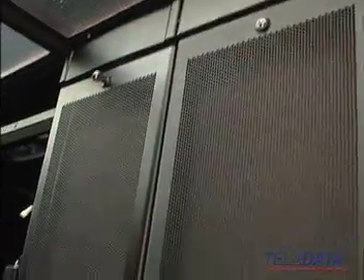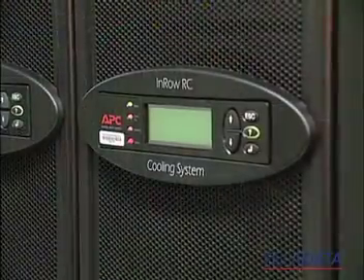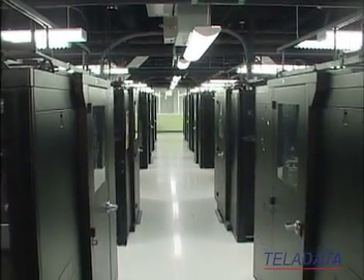This is the hot aisle. Oh, I can feel it. It's hot, all right. So it's between 95 and 105 degrees depending on what kind of equipment is in here. Air conditioners in row with the actual equipment. So the servers are sucking in the actual cold air. They warm up as it comes out here, and then it gets sucked back through both of these units, and it blows out cold air in the front. And so it can actually dynamically go up and down based on whatever it's sensing with the load itself. This is the kind of stuff that enables you to make changes or turn on a dime.